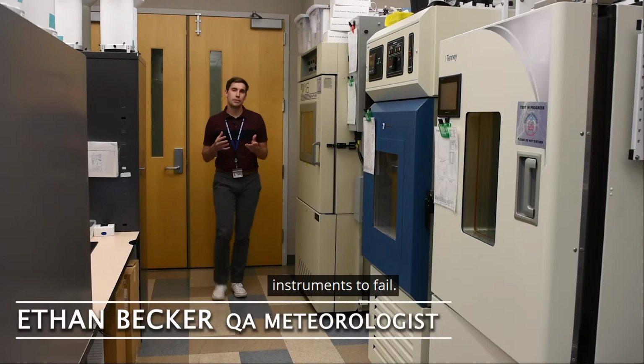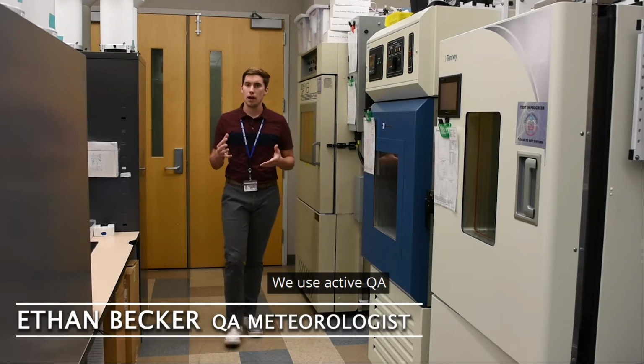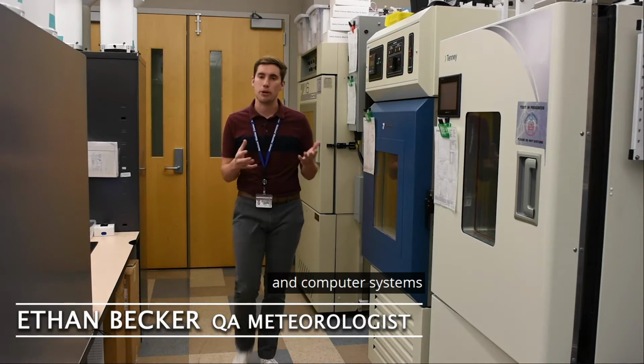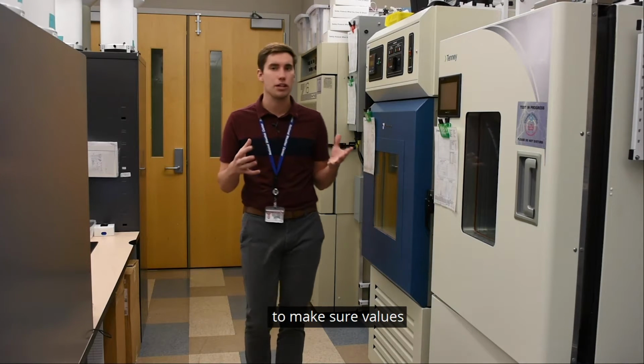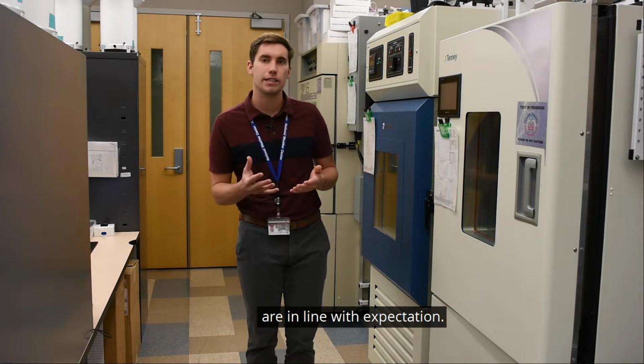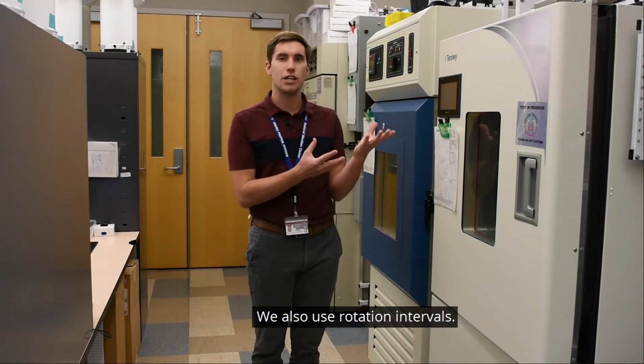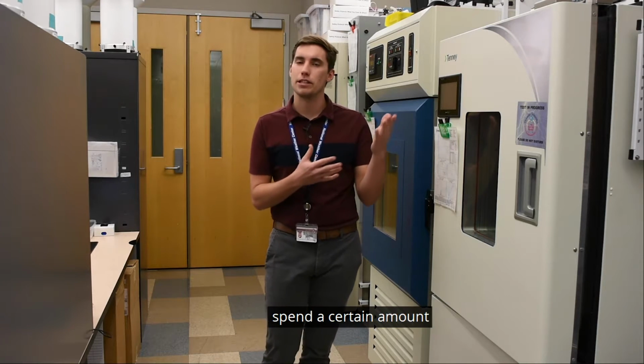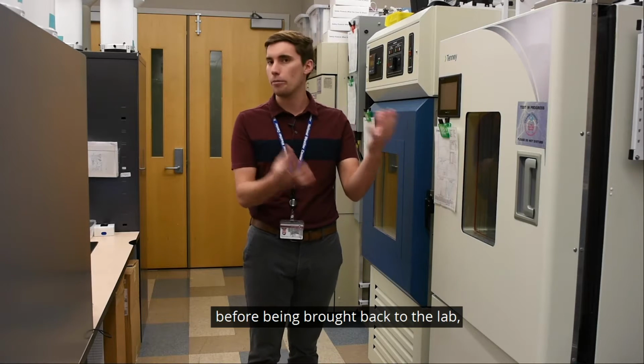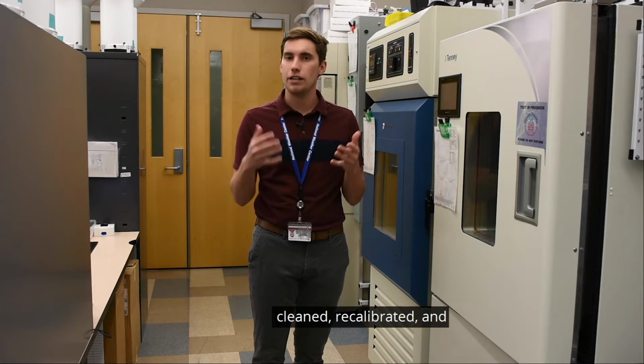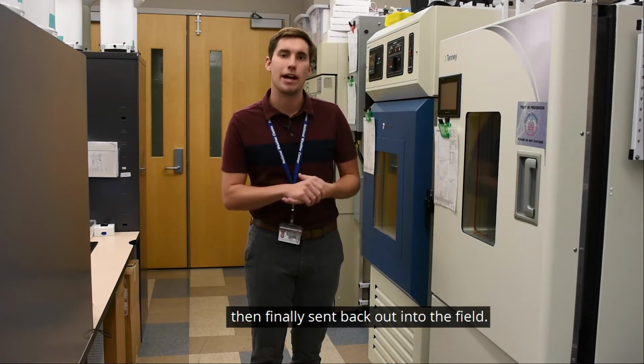We don't wait for instruments to fail. We use active QA, where QA meteorologists and computer systems are checking the data to make sure the values are in line with expectation. We also use rotation intervals. A sensor will only spend a certain amount of time in the field before being brought back to the lab, cleaned, recalibrated, and then finally sent back out into the field.